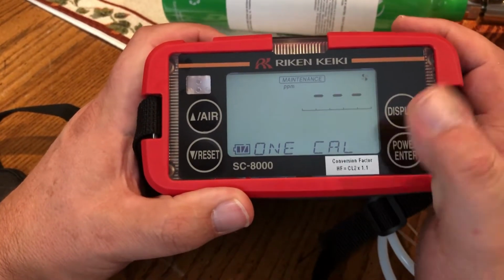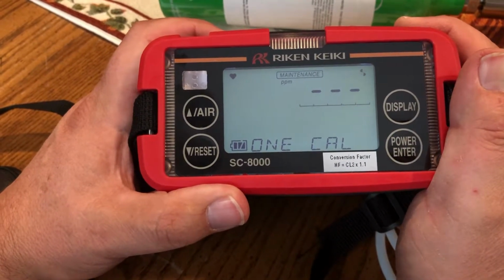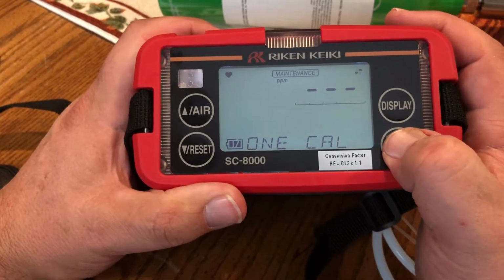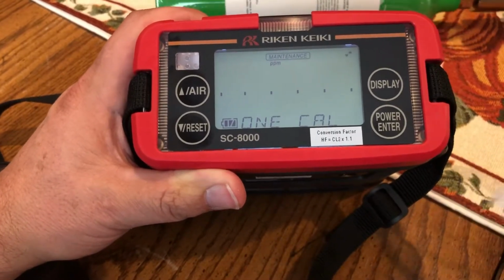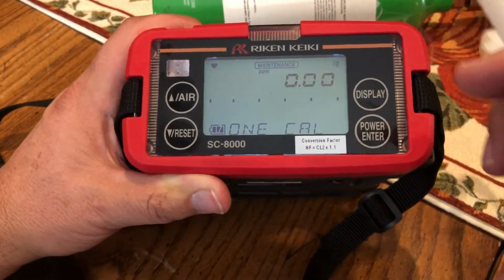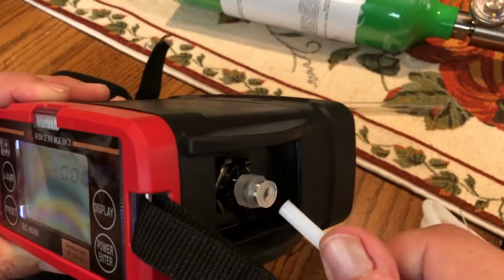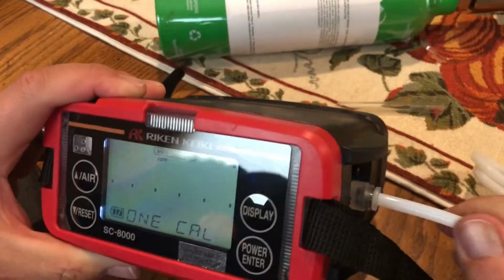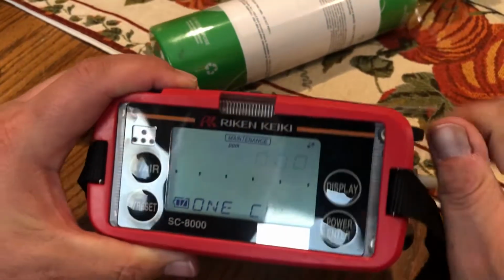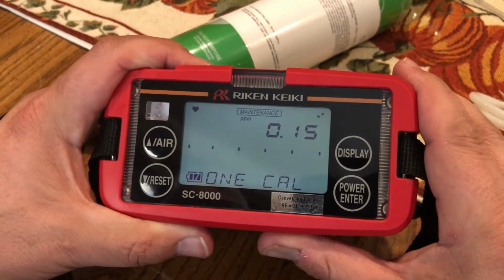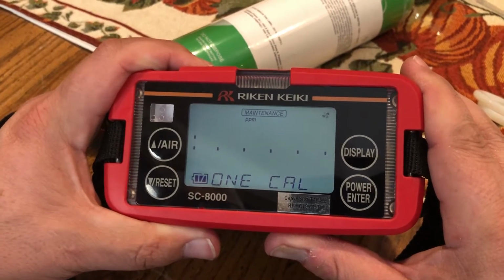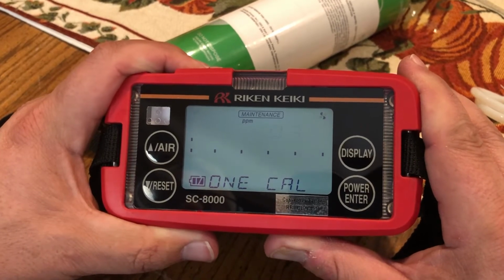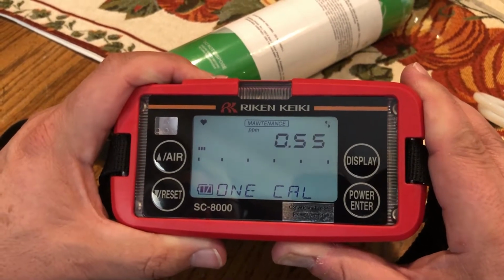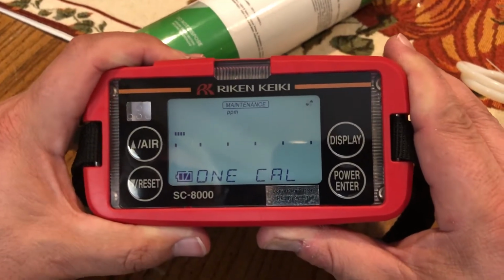By hitting enter, we enter into the calibration mode. By hitting enter again, the unit is now looking for gas. Please use the gas provided with a tube and press it into the gas inlet. And from here, we are going to wait 2 minutes for those values to get to 2.2. Because this takes too long for the video, I'm going to stop the video here and we will pick up with another video. Thank you.